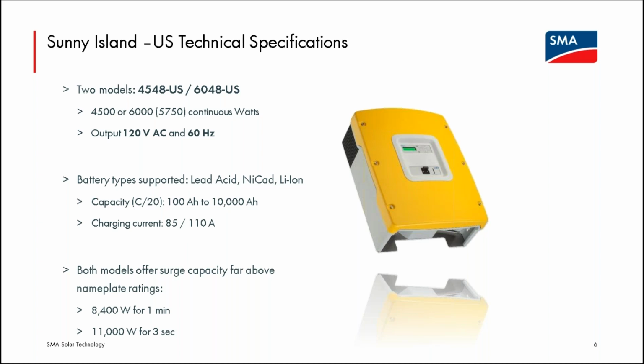When you use a lead acid battery bank with the Sunny Island, generally manufacturers of the lead acid battery banks don't want those to be discharged more than 50%. So that low end is not very big. The BYD batteries for the Sunny Boy storage can be 10 kilowatt hours, almost all usable in one box. So the low end is a quite small battery bank and would be really capable of just running smaller loads, but the range is huge.